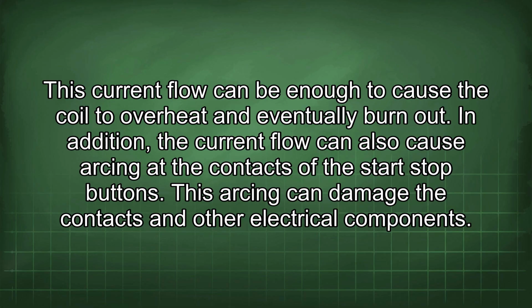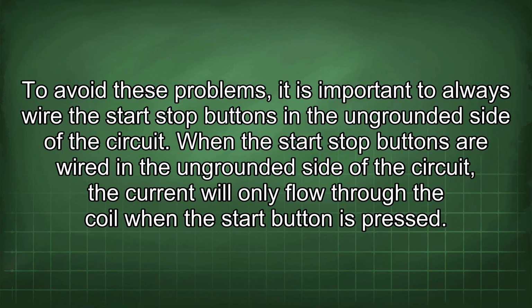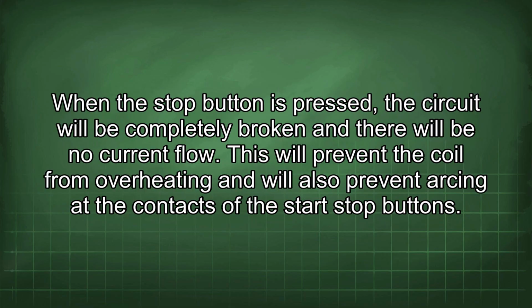In addition, the current flow can also cause arcing at the contacts of the start-stop buttons. This arcing can damage the contacts and other electrical components. To avoid these problems, it is important to always wire the start-stop buttons in the ungrounded side of the circuit. When wired in the ungrounded side, the current will only flow through the coil when the start button is pressed. When the stop button is pressed, the circuit will be completely broken and there will be no current flow. This will prevent the coil from overheating and will also prevent arcing at the contacts of the start-stop buttons.